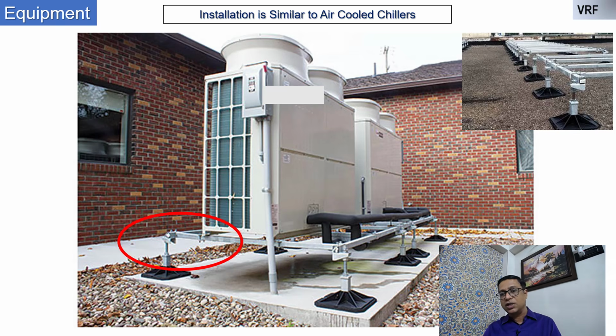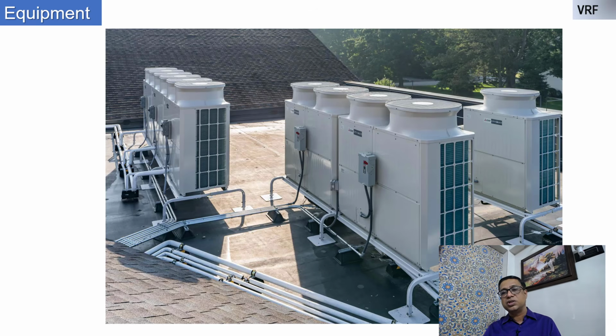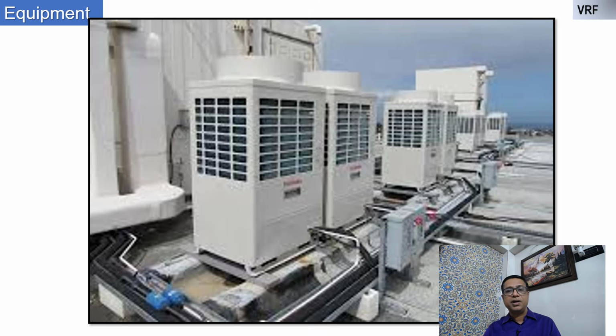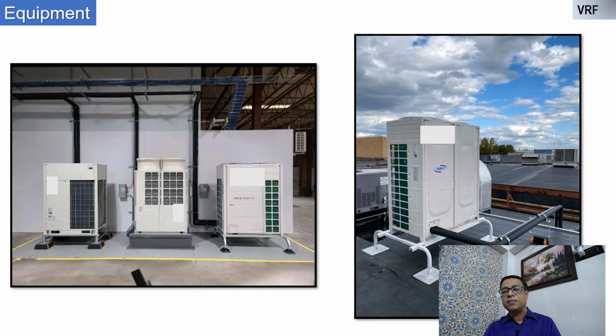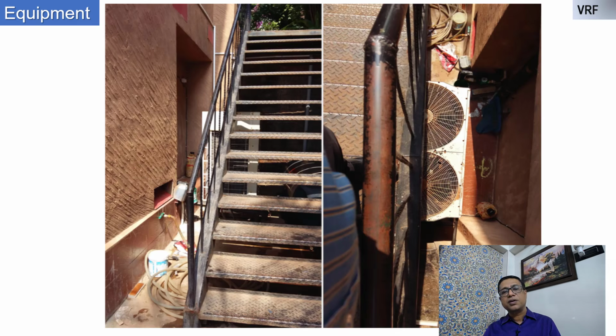It is similar to what we do for air cooled chillers. The outdoor units are outside, and they need a lot of air for circulation. They can be mounted on a prefixed or prefabricated support, so you can do the installation very fast, because a lot of things are prefabricated outside. You can see various types of prefabrication here, but this is not the way to install the machines. If you put something on top of these machines where air circulation becomes an issue, your system will not work, it will get derated, and you will consume more and more energy. So the whole aspect of getting VRF for reduced energy consumption will not happen.